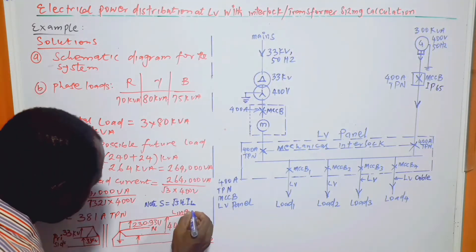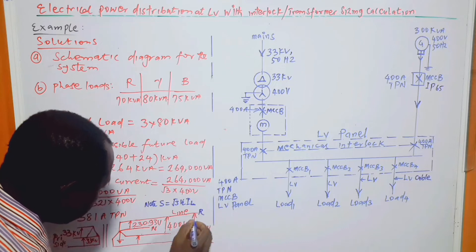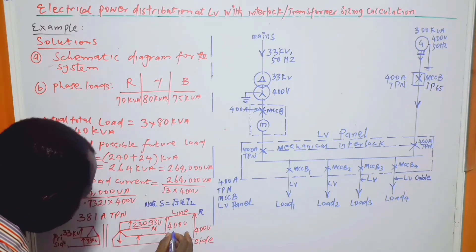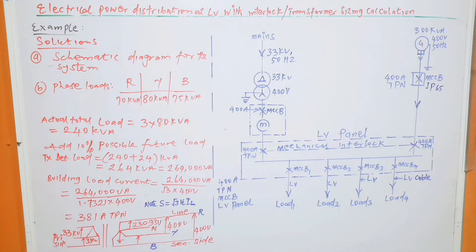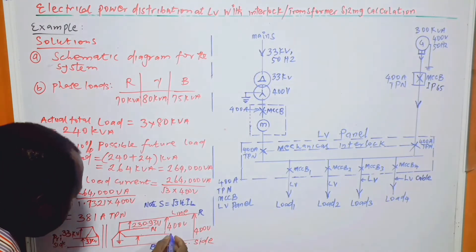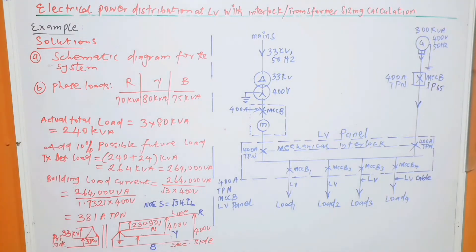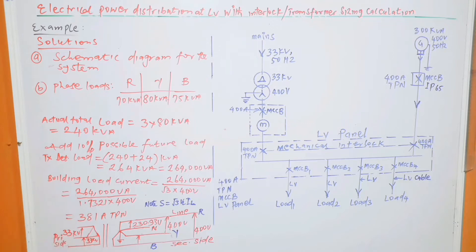So this is 381, the current flowing in this phase also is 381, and also in this phase 381. So actually, we can call this one the red phase, and this one will be yellow phase, and this will be blue phase. So this is the secondary side, and this is the primary side with 33 kV line to line, and that is the answer to part B of the question.